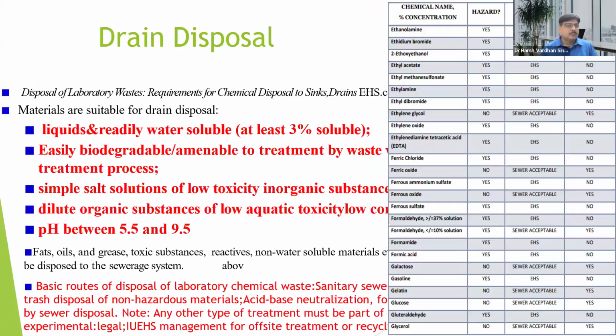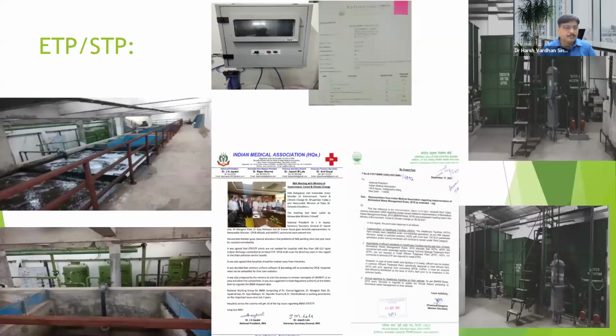Then there's drain disposal - certain chemicals are sewer acceptable, certain are not, so keep that in mind. The pH of the effluent should be environmentally sound, between 5.5 and 9.5. You can test and neutralize it - for example, ascorbic acid is a good edible acid you can use for neutralizing if your pH is beyond 9.5.